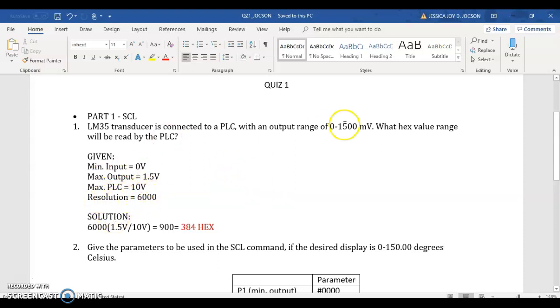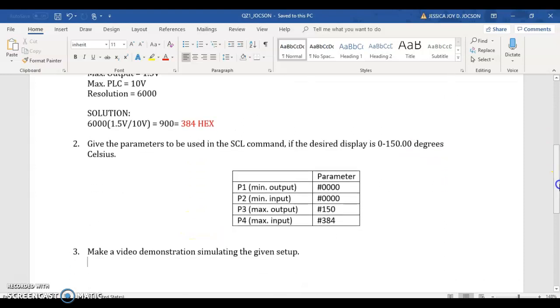So what is the hex value range that will be read by the PLC? Multiplying the voltage, the maximum voltage output, divided by the maximum voltage of the PLC, times the resolution, is equal to 900 in decimal, and if converted to hex, it will be 384. These are the parameters to be used.